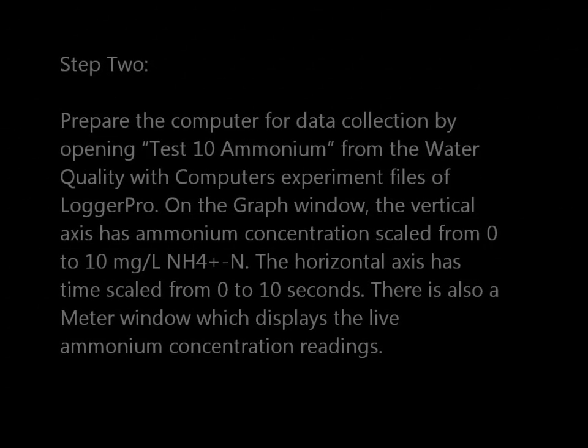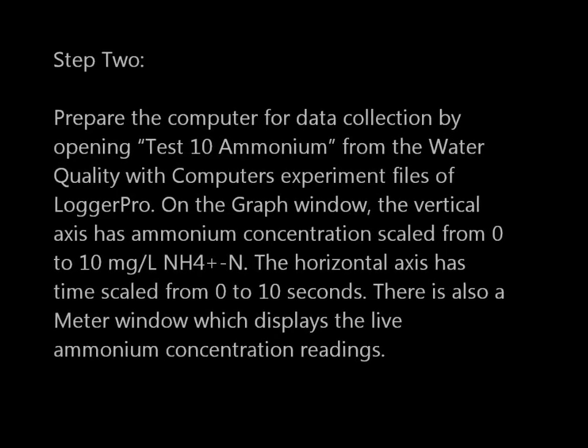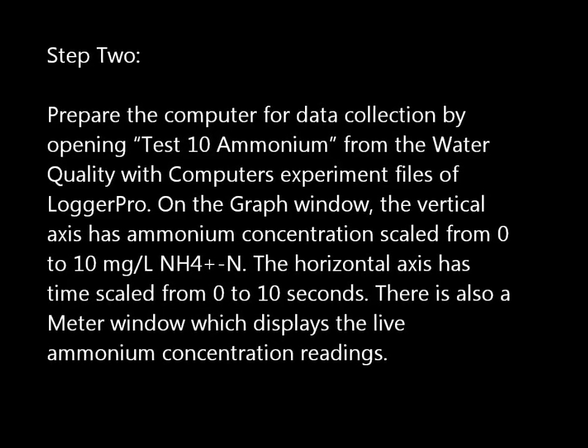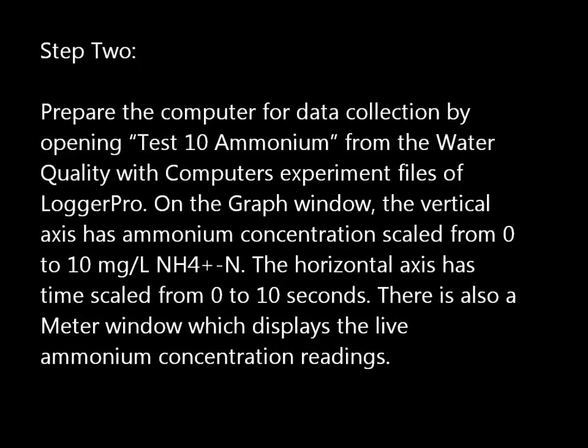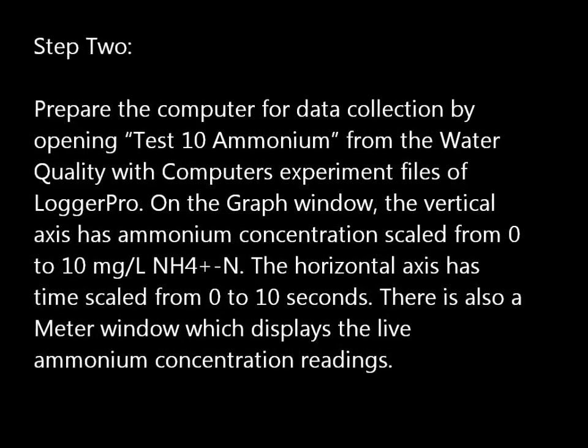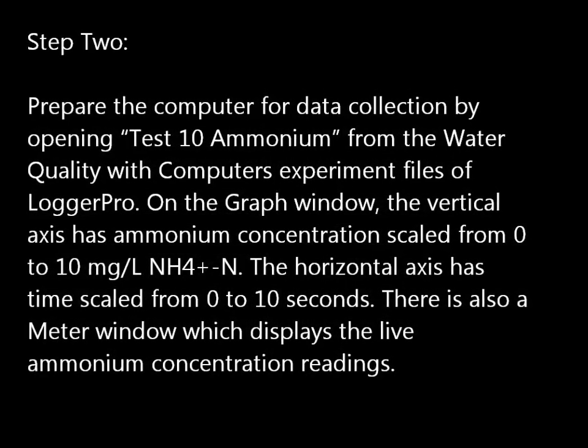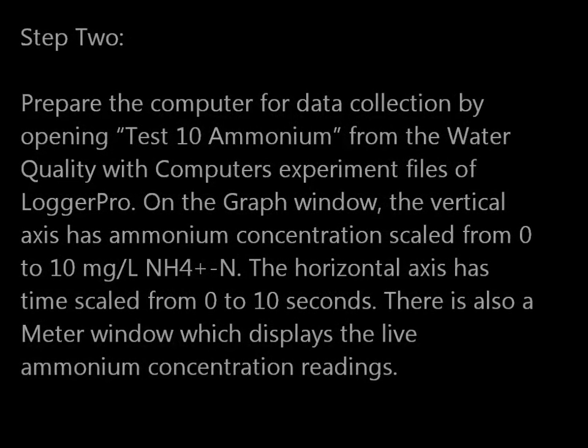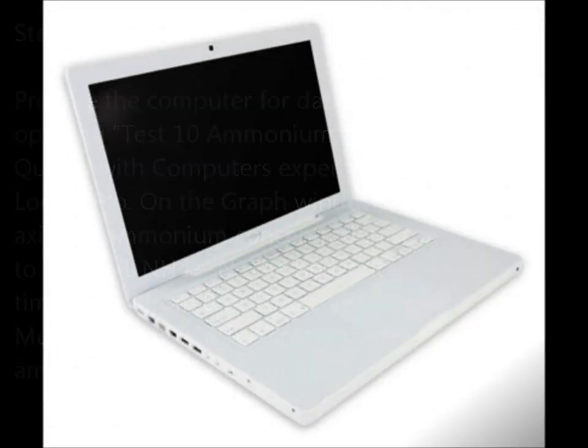Step 2. Prepare the computer for data collection by opening Test 10 Ammonium from the Water Quality with Computers experiment files of LoggerPro. On the graph window, the vertical axis has ammonium concentration scaled from 0 to 10 milligrams per liter. The horizontal axis has time scaled from 0 to 10 seconds. There's also a meter window.